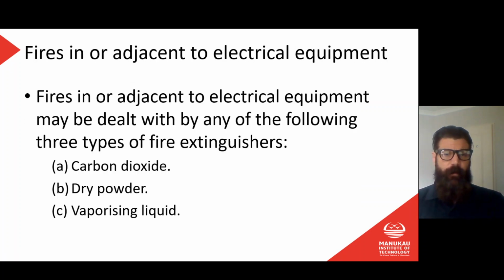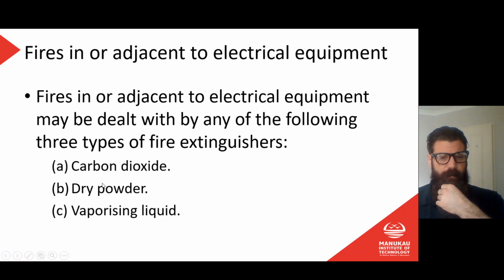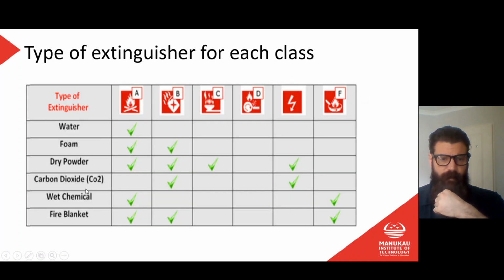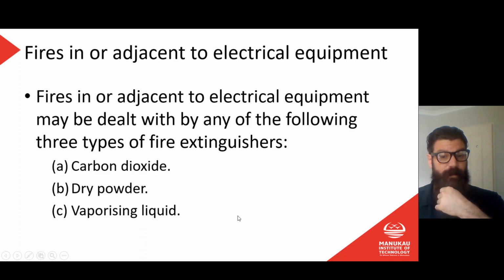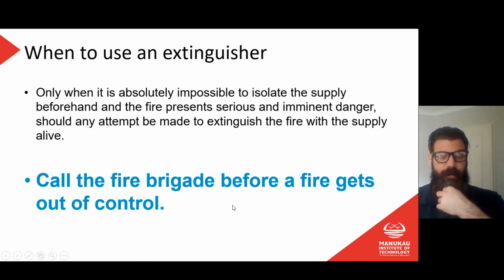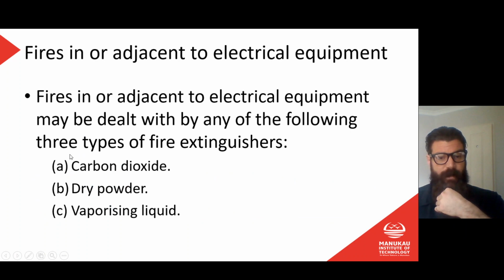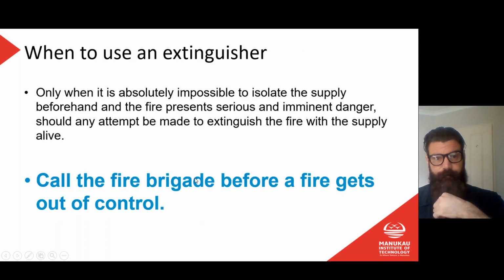So a little bit more on fires with electrical equipment, because obviously that's important to us as electricians. Fires in or adjacent to electrical equipment may be dealt with by any of the following three types of fire extinguishers: carbon dioxide, dry powder, and vaporizing liquid. I don't think we saw vaporizing liquid before. Let me just scroll back. It's electrical. Okay, so we didn't talk about vaporizing liquid. Not something that I've come across. So generally we're talking about carbon dioxide and dry powder.